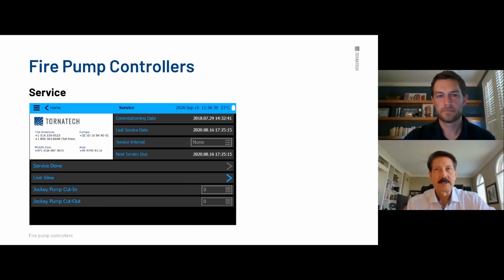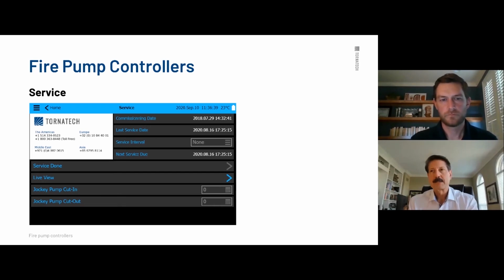If you don't input the cut in, cut out of the jockey, your accuracy range might be 85–90%. By putting it in, it's going to be much higher, 95 plus. I mean, probably closer to 98–99. I'm just ballparking. It does it by the algorithms. It's sensing pressure decrease, increase. And at the same time, like Cole mentioned, in your event logs and your data, it's tracking statistics. It's tracking the number of operations the jockey is actually cycling on and off. So it's tracking that too. Right.